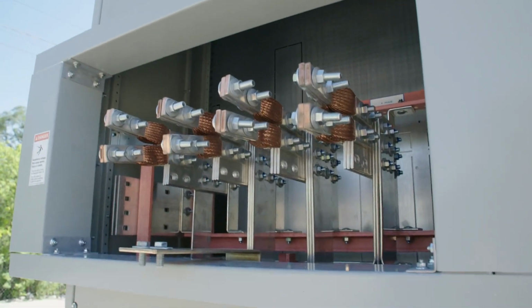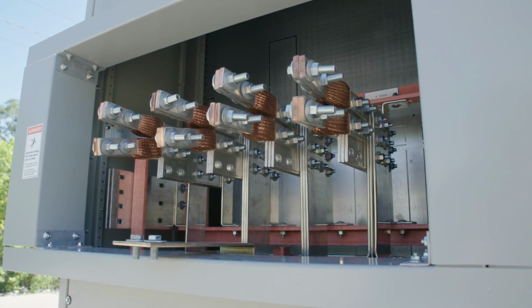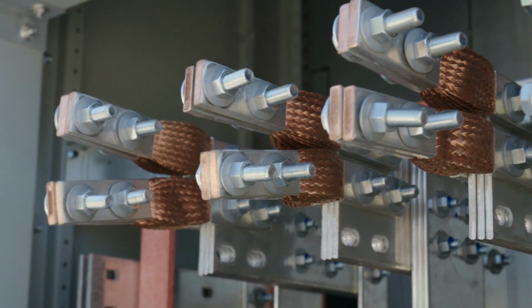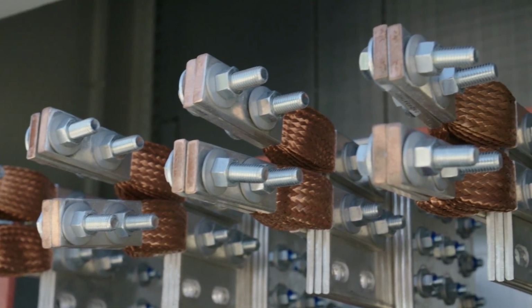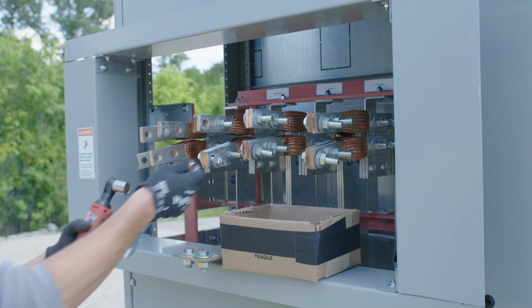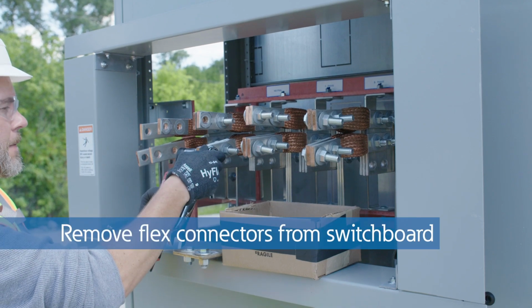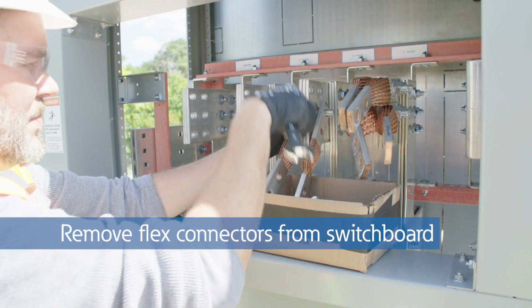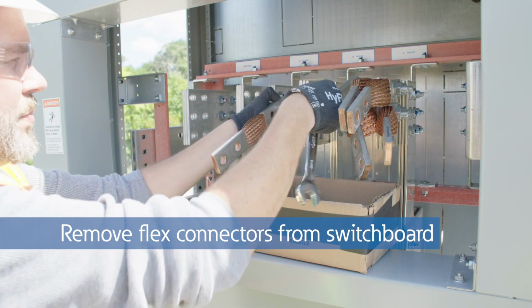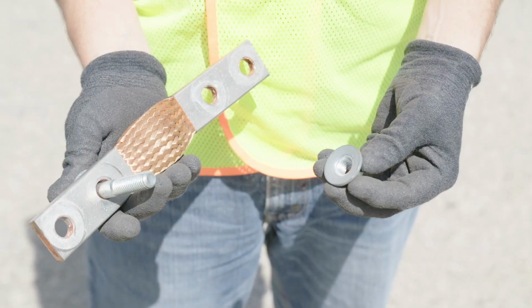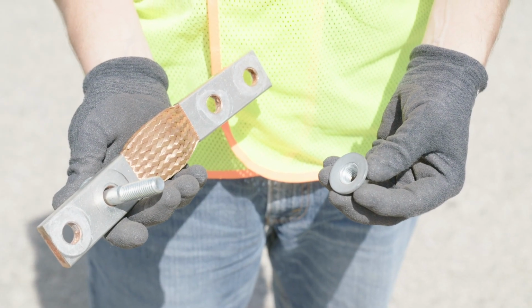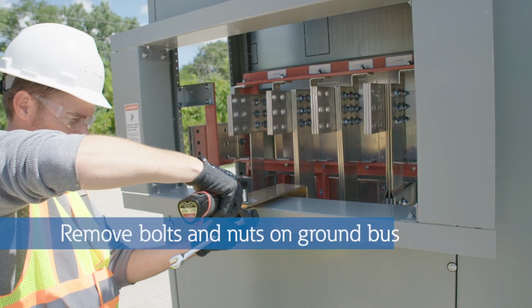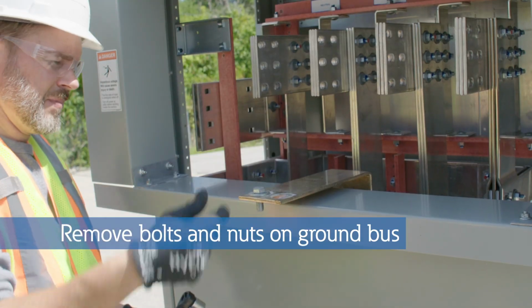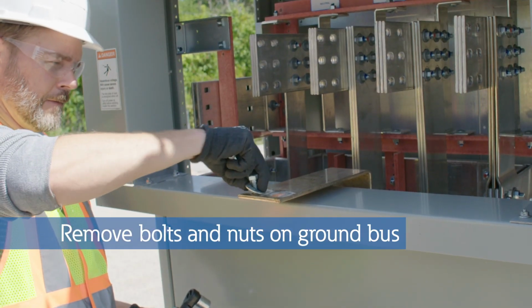The flexible connectors used for the close couple bus connections are typically factory installed on the bus conductors at the switchboard flange. For ease of installation, we suggest unbolting and removing the flex connectors from the switchboard and installing them on the transformer flange bushing extensions. Finally, remove the 2 bolts and nuts installed on the switchgear ground bus at the transformer throat.